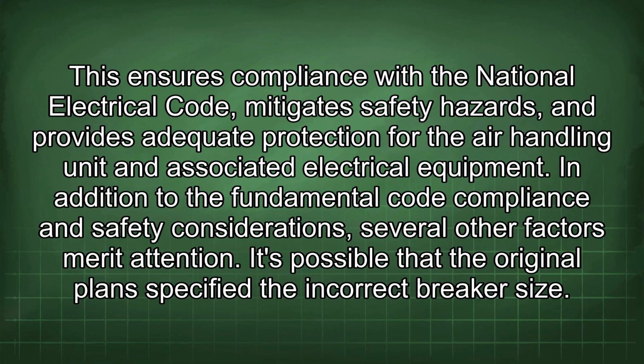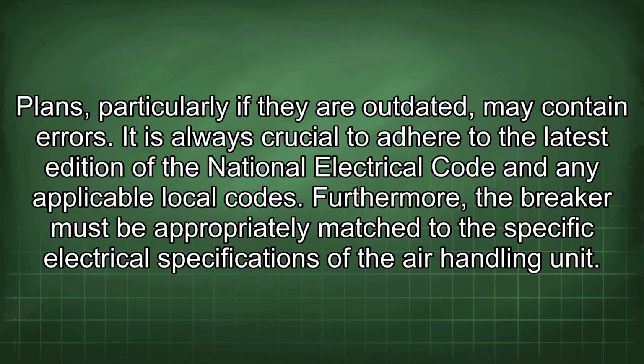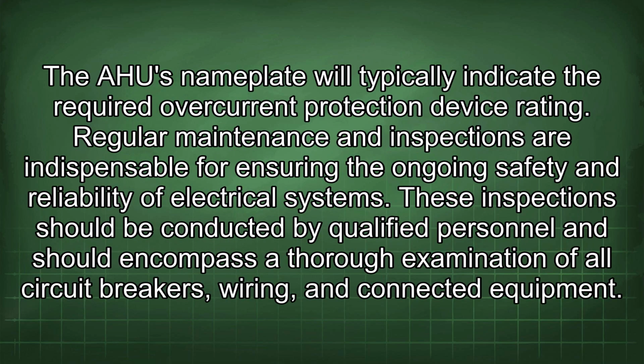It's possible that the original plans specified the incorrect breaker size. Plans, particularly if they are outdated, may contain errors. It is always crucial to adhere to the latest edition of the National Electrical Code and any applicable local codes. Furthermore, the breaker must be appropriately matched to the specific electrical specifications of the air handling unit. The AHU nameplate will typically indicate the required overcurrent protection device rating.